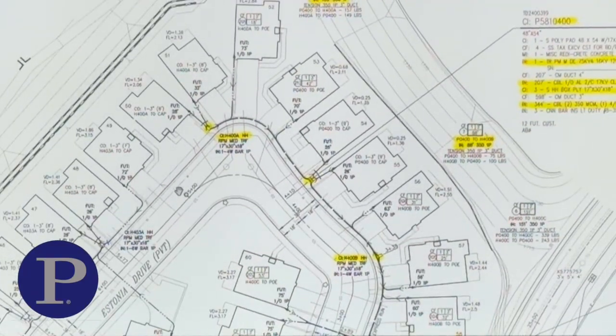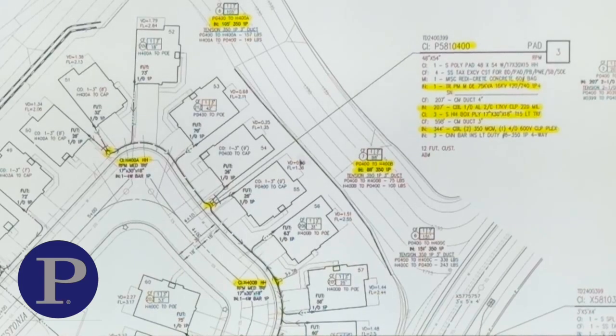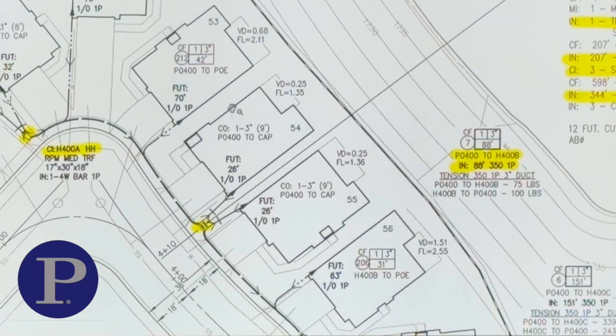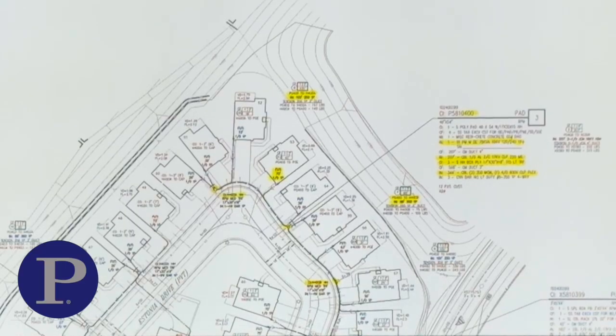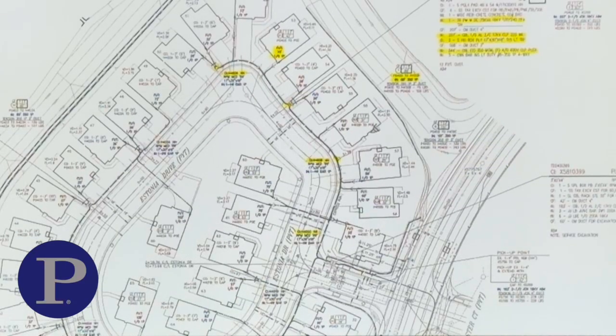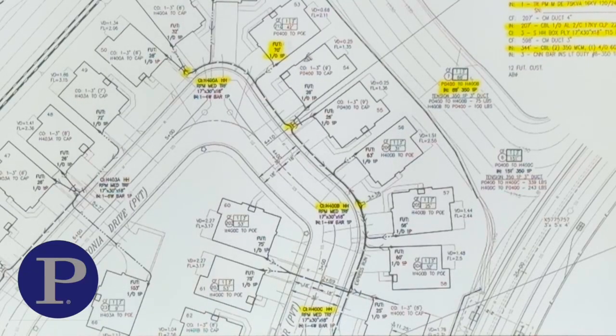In addition to that, if we take a look at the service cable pulls, every lot with a house on it is going to have the information of what we're pulling right here. We've got 1-aught cable, single phase 1-aught. We've got 70 feet. This cable callout shows it as a future, which means it's not going in on this mainline work order. If you've got model lots, sometimes they will include them on what's called a Rule 15. This mainline work is considered a Rule 15 in Southern California Edison. The services are what's known as a Rule 16. And when it shows future, that's going to go in on a future Rule 16 work order.